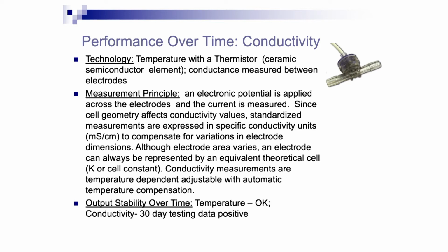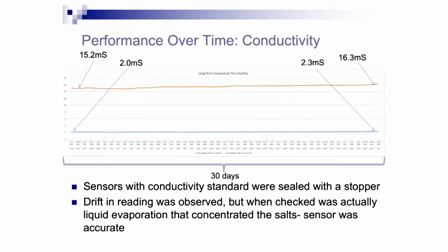We looked at the testing over time, mainly interested in drift. And we did see a slight upward drift over 30 days, but then we realized when we did our final measurements, there was actually some slight evaporation, which concentrated the salts. And upon second testing, we realized they actually hadn't changed. So that built us up a lot of confidence. There's more testing going onwards for that.